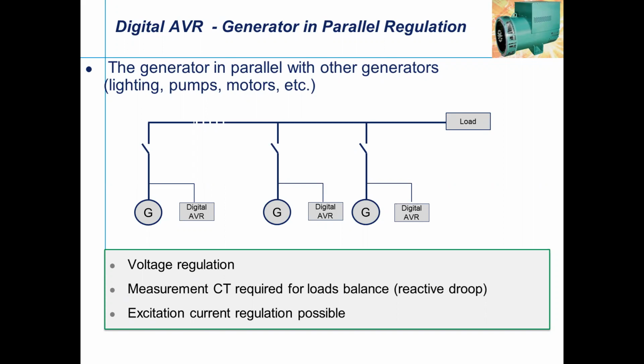And of course, what I was mentioning, the CT is a very, very important component to balance the load. I was showing in the previous slides where the reactive or active droop, what you can want to do, we can play with that. If there is a load demand, we can also give a reactive demand. Excitation current regulation is possible. That is one of the requirements for the bigger generators where your integral system is there.